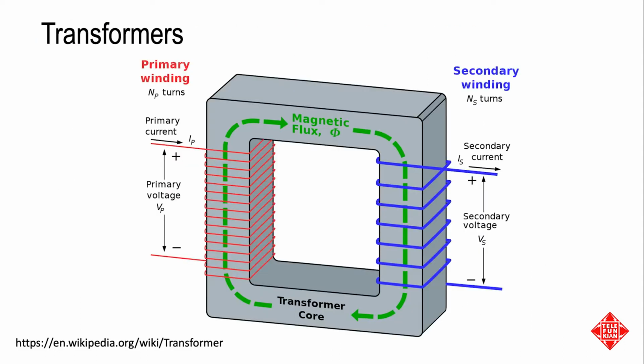The reason we're looking for a replacement transformer has to do with the way transformers work. The transformer in the CR-78 is a voltage-reducing transformer that works by passing the line voltage through a primary winding that's wound around a ferrous core. When current flows through the primary winding, it induces a magnetic field, which in turn induces a proportional current through the secondary winding. The relationship between the voltage present across the primary winding and the voltage induced in the secondary winding is determined by the number of turns in each respective winding.